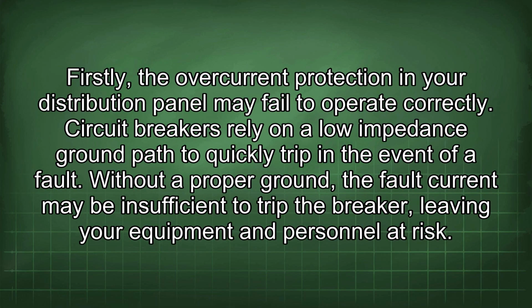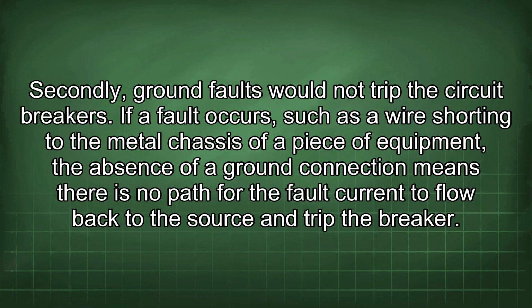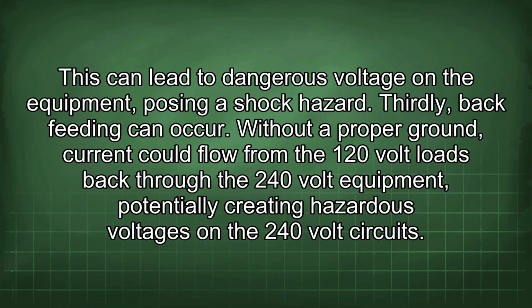Firstly, the overcurrent protection in your distribution panel may fail to operate correctly. Circuit breakers rely on a low impedance ground path to quickly trip in the event of a fault. Without a proper ground, the fault current may be insufficient to trip the breaker, leaving your equipment and personnel at risk. Secondly, ground faults would not trip the circuit breakers. If a fault occurs, such as a wire shorting to the metal chassis of a piece of equipment, the absence of a ground connection means there is no path for the fault current to flow back to the source and trip the breaker. This can lead to dangerous voltage on the equipment, posing a shock hazard.